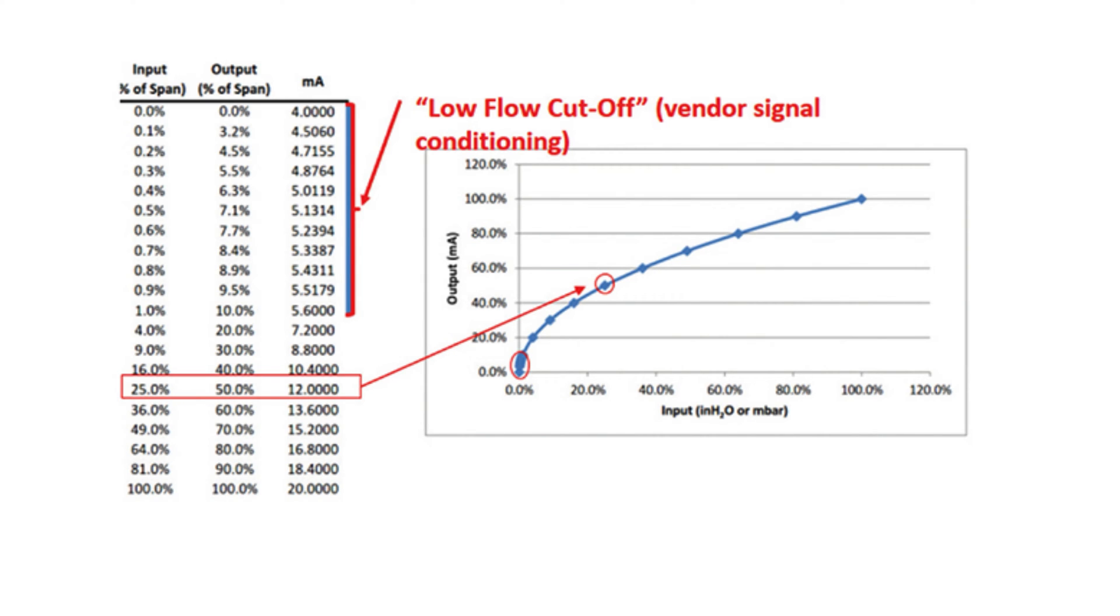A low flow cutoff at a flow rate of 10% corresponds to an output of 5.6 mA. So between 4 and 5.6 mA there is no useful measurement possible because of too much inaccuracy. All of that will have consequences on the calibration of our DP flow transmitter.